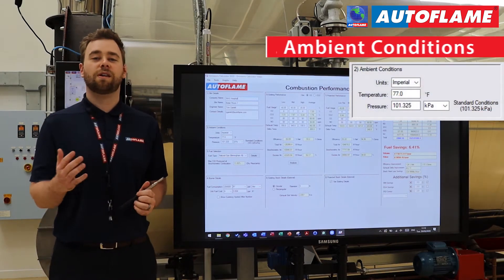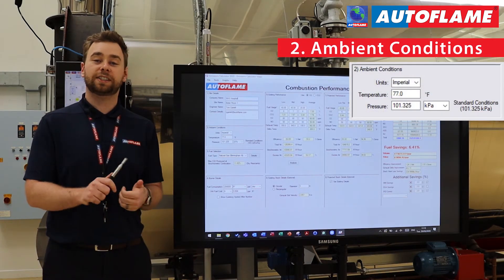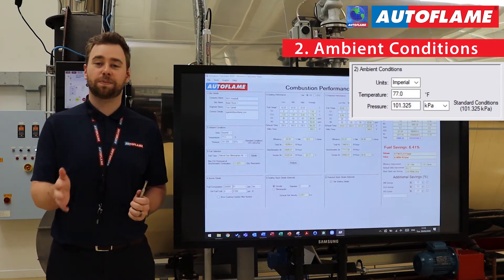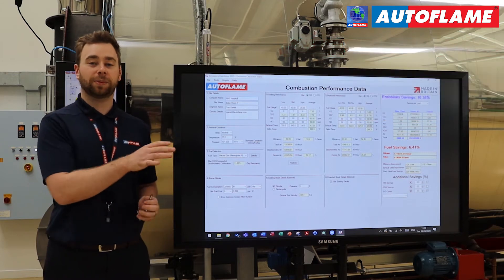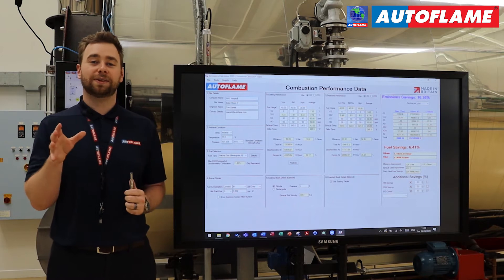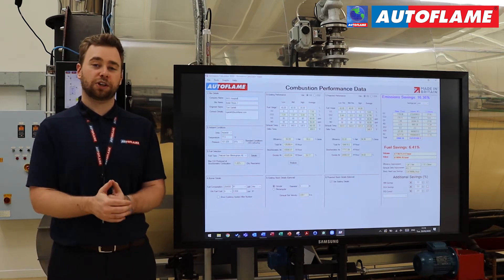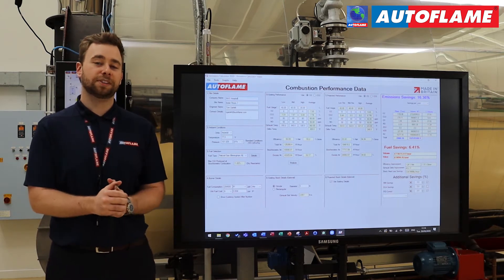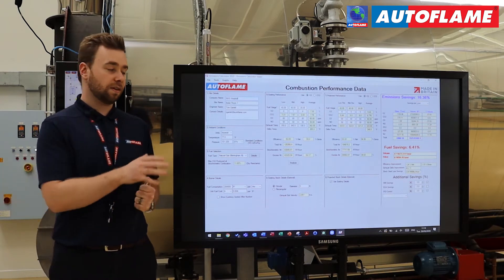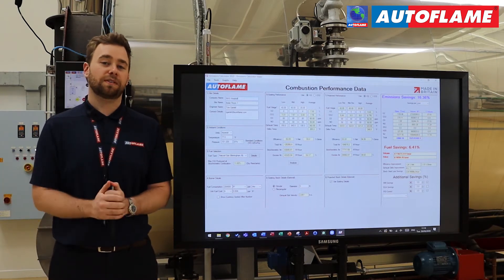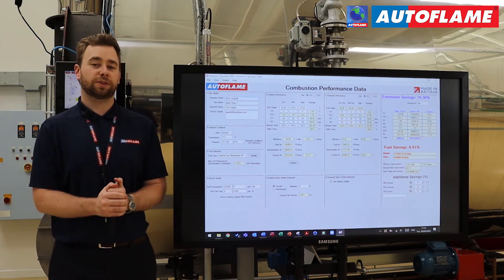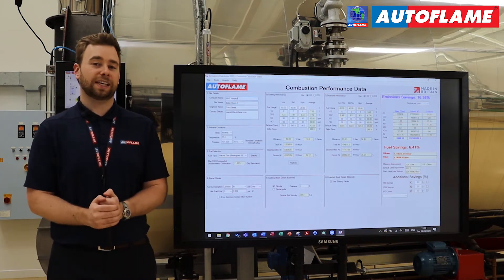Section two covers your ambient conditions. This is where you define your units — in our case we'll be using Imperial. You also need to input your ambient temperature; we're going to be using 77 degrees F. Then you need to input your ambient pressure. On the previous emissions calculator this was an offset from standard sea level, but this is now an absolute value — so for example in kilopascals it's 101.325, which is ambient sea level.